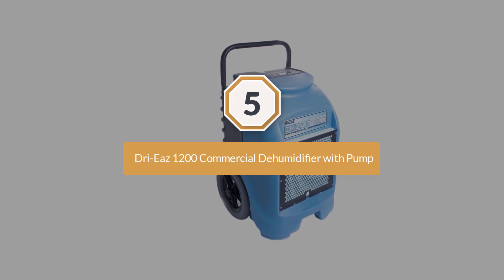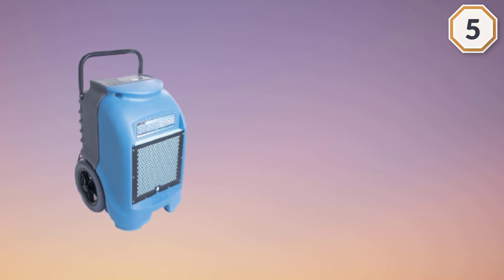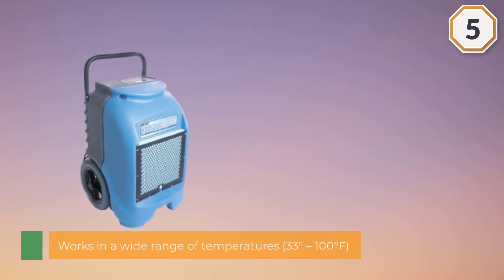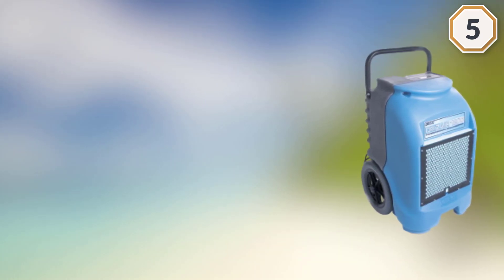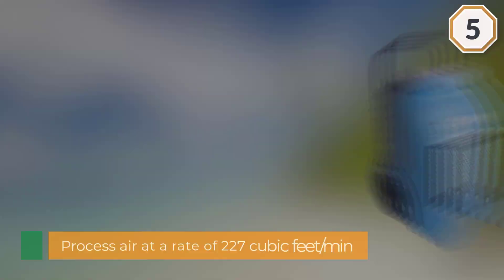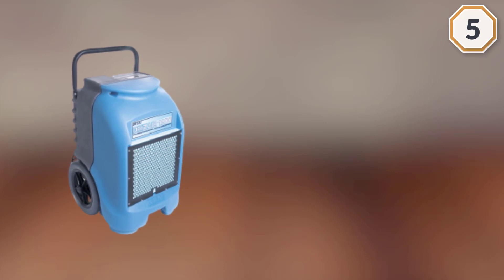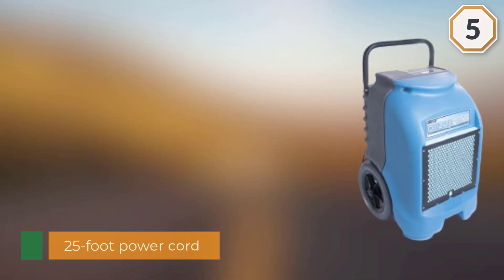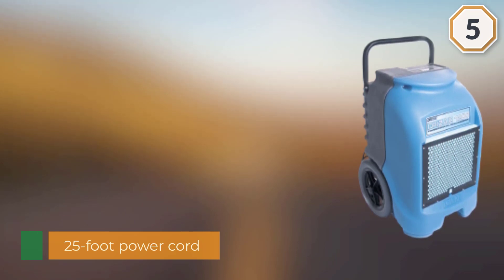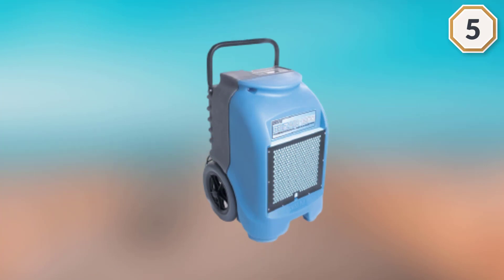The Dri-Eaz 1200 operates at a wide variety of temperatures, from as low as 33 degrees Fahrenheit to as high as 100 degrees Fahrenheit. It processes air at a rate of 227 cubic feet per minute and draws 6.4 amps on a 115-volt power supply. It has a 25-foot power cord for easy access to a power outlet from across a large crawlspace, and features a built-in duct attachment ring for improved air quality.